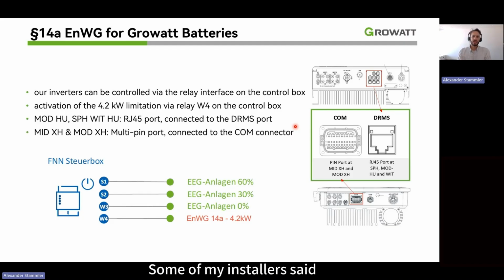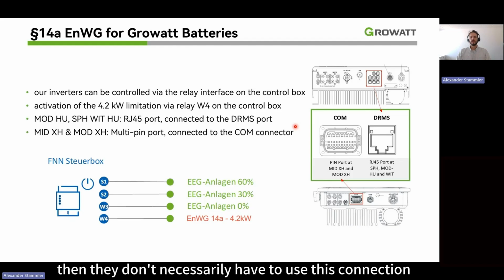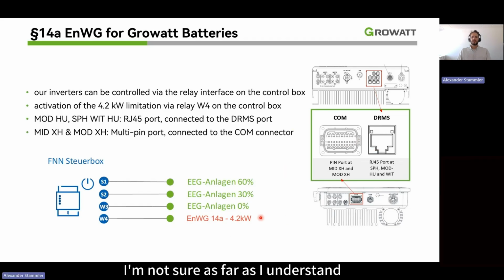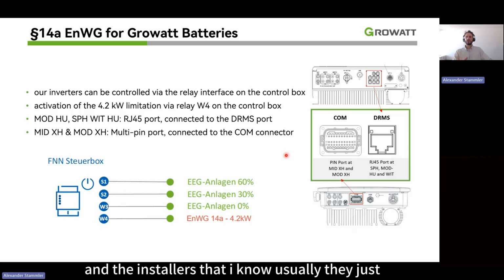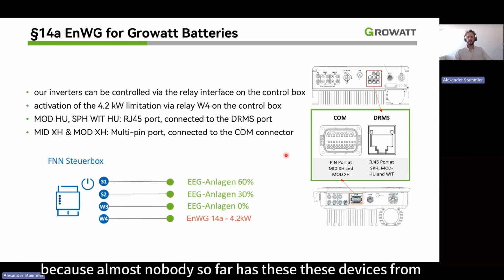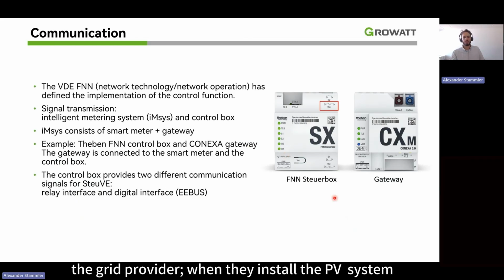Some of my installers said, if I simply put the setting in the inverter, no grid charging allowed, then they don't necessarily have to use this connection. I'm not sure. As far as I understand, it has to be something that the end user is not able to set. So for example, if it's only a setting, the end user can unset or disable the setting, and then the battery would be able to use grid power to charge.